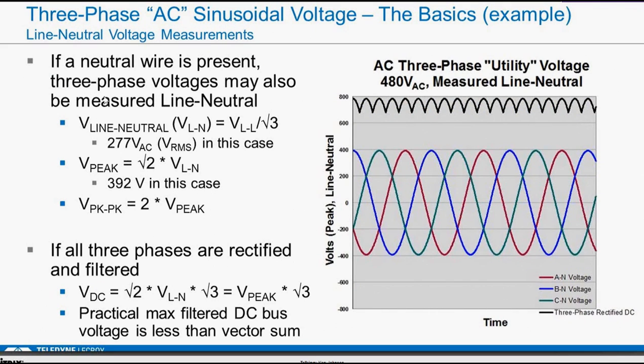So if you have a neutral wire present, you can measure the voltage line to neutral. That would just be, as we described before, the line-to-line voltage divided by the square root of 3. So on a 480-volt AC system, the line-to-neutral voltage is only 277 volts AC. Then in this case, if you wanted the peak line-to-neutral voltage, it's square root of 2 times the line-to-neutral voltage, which is, in this case, a little under 400 volts, and the peak-to-peak would be 2 times that, or a little under 800 volts.